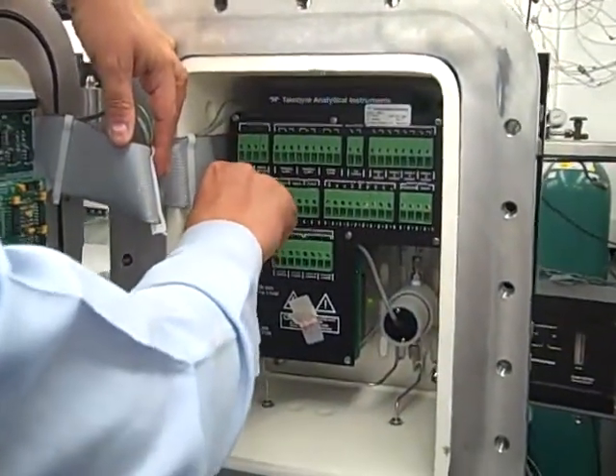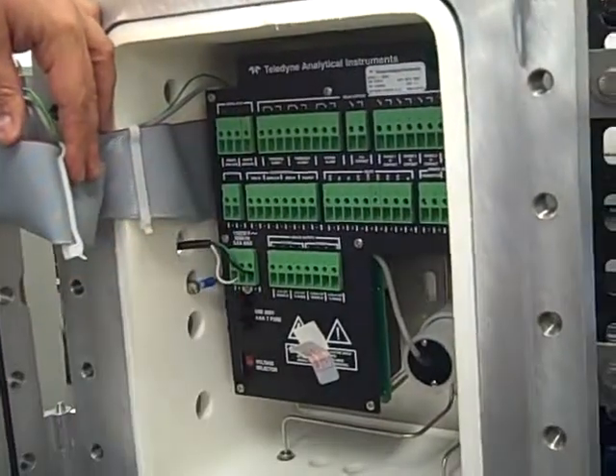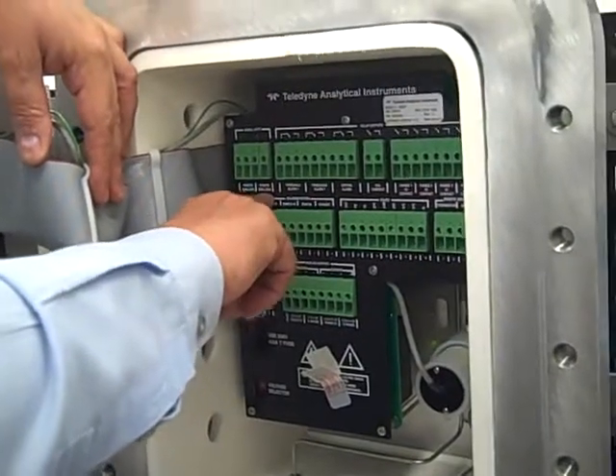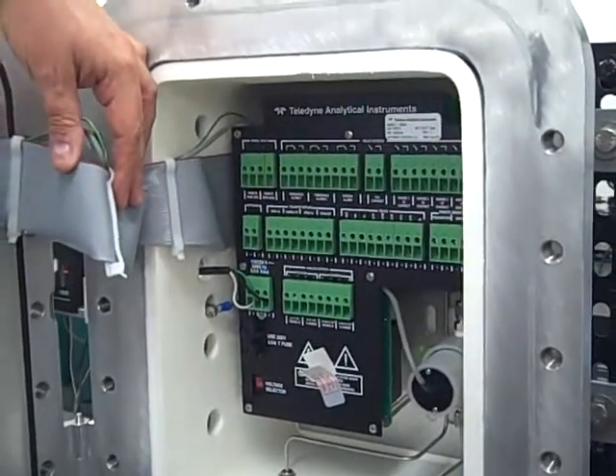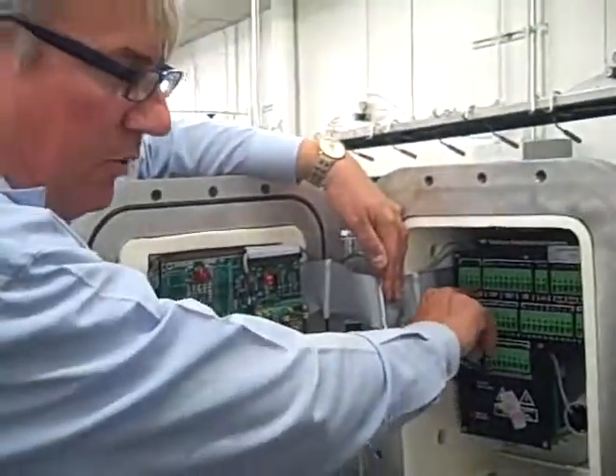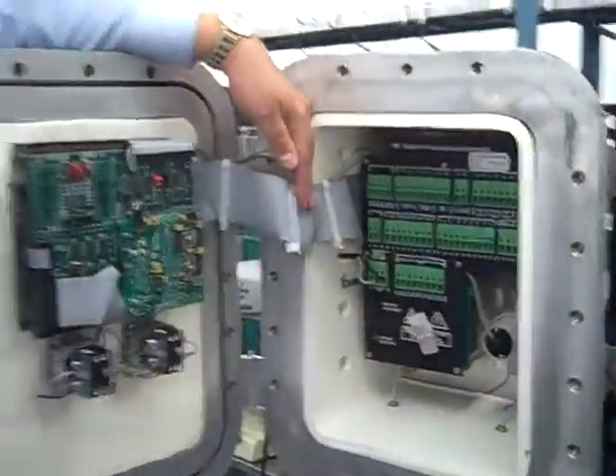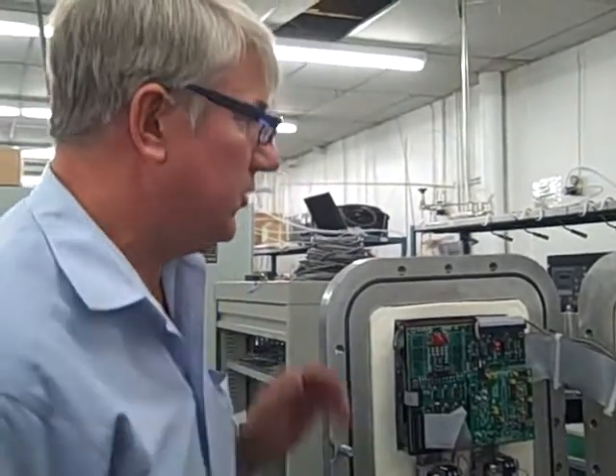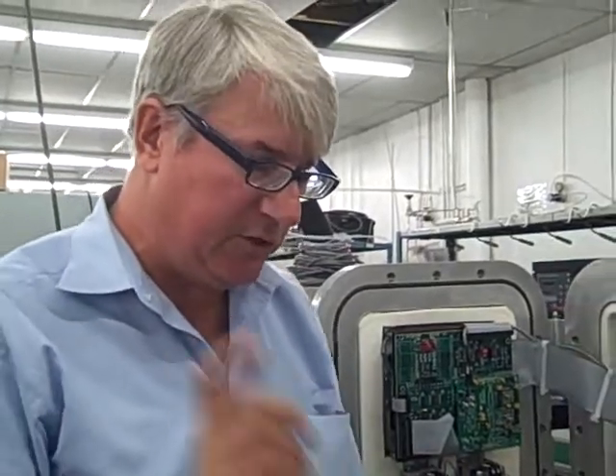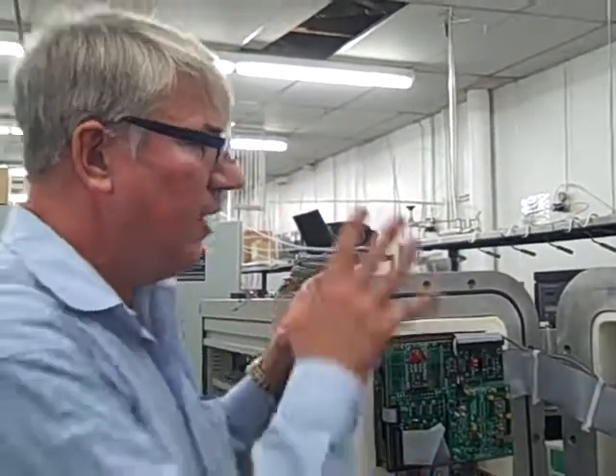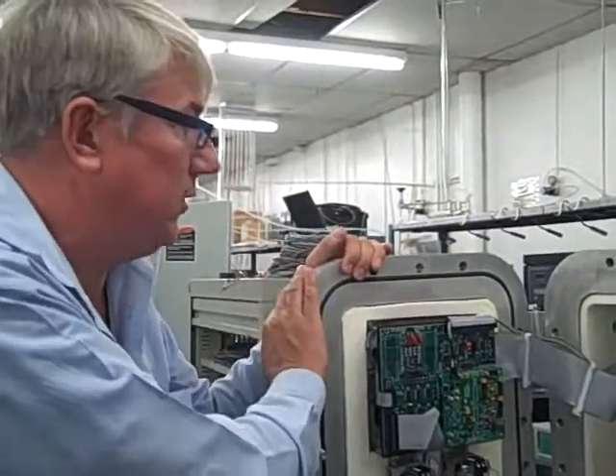So there's an input for remote span if you want to tell the unit to go into a span mode remotely. There's also a remote zero. Now for percent analyzers, you never need to zero them, so you would never do that for a 3020P. For a 3020T, it's the same thing. There's no need to zero the unit, in most cases. The reason we have a zero there is because the sensor, when it's exposed to pure nitrogen, will come down to a level that is typically about 100 parts per billion. So for customers for whom that error is important, you can remove that error by doing a zero cycle. Some sensors will come down to 100 parts per billion, some to 200, some to 50, so there's variation there. But generally speaking, 99% of our customers for these units don't need to zero them.